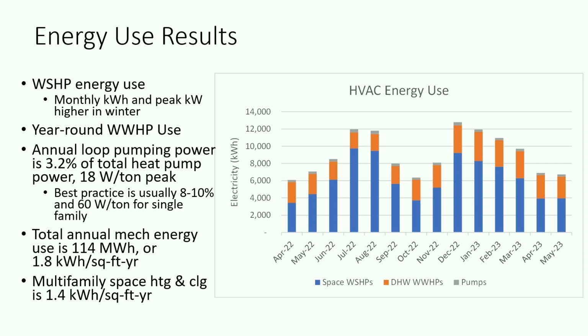But really what was kind of extraordinary about this compared to other systems I've ever monitored is that the pumping power was extremely low. The peak rate was about 18 watts per installed ton, and normal systems are on the order of 60 watts. I think the Clean Heat program says you have to be under 60 watts per ton. So this was quite a bit lower than that. And in best practice, usually you might use 10% of the heat pump energy for pumping. Here we were more like 3% because it was a variable speed system.